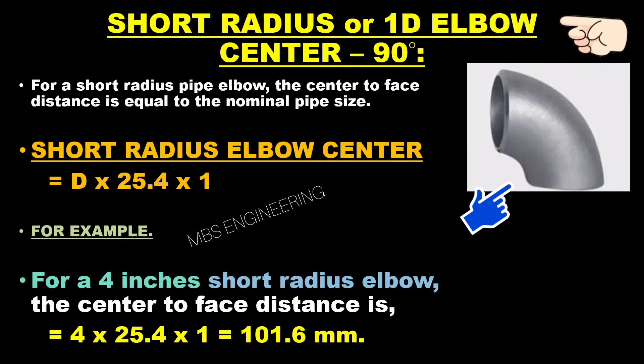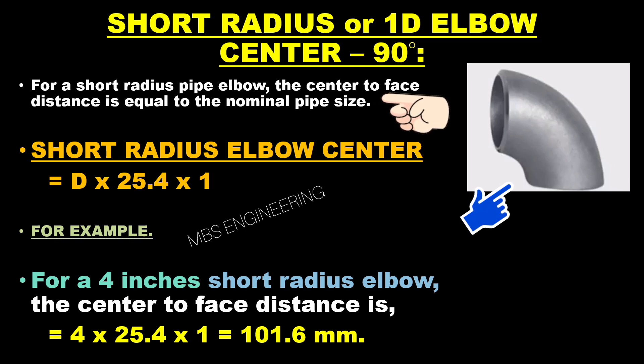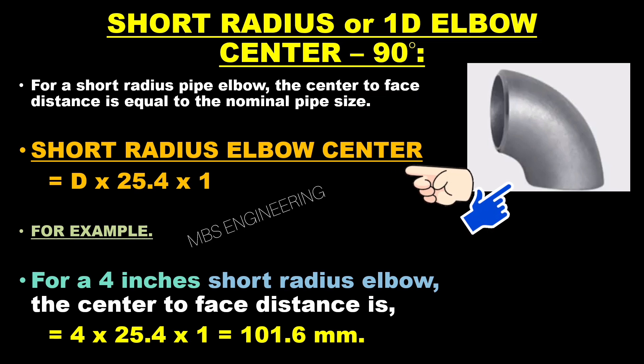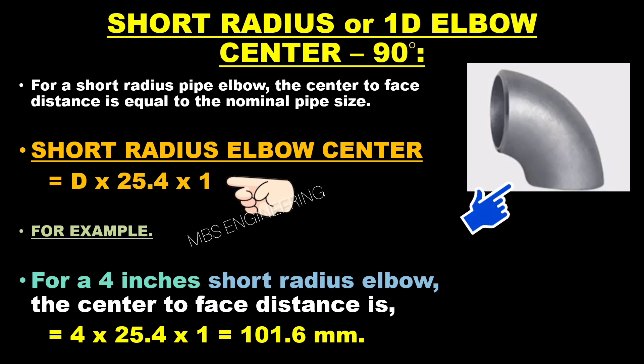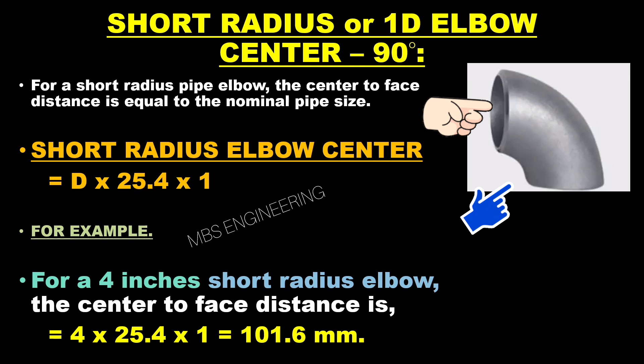Next, we will calculate the elbow pipe center for short type or 1D elbow at 90 degrees. For a short radius pipe elbow, the center-to-face distance is equal to the nominal pipe size. The formula is: Short Radius Elbow Center = D × 25.4 × 1, where D is the diameter of the elbow in inches.